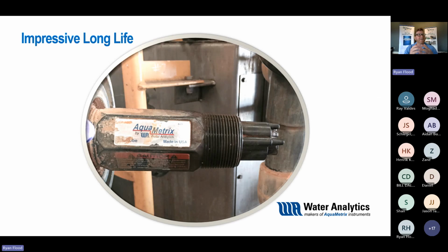We have an impressive long life with our sensors, so for the most part this end-of-life consideration is way down the road. The efficiency reading lets you identify this as an expert to your customers or others in your facility, showing you know when maintenance is needed. If you perform a simple calibration and see it might be time to replace that salt bridge, it's an indicator you need to do a bit more to keep that sensor running optimally for years to come.